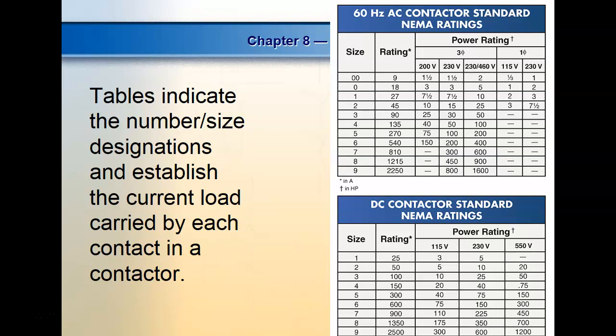Size 6, I could run a what? A 150 horsepower motor on 200 volts. I could run a 200 horsepower on 230 volts. I could run a 400 horsepower on 460, and then these things are not rated for single phase. So why can we run a bigger horsepower motor on a higher voltage?